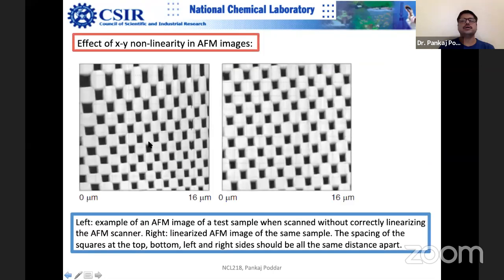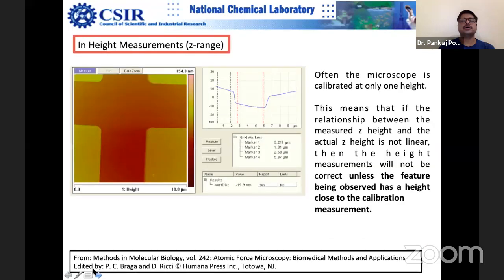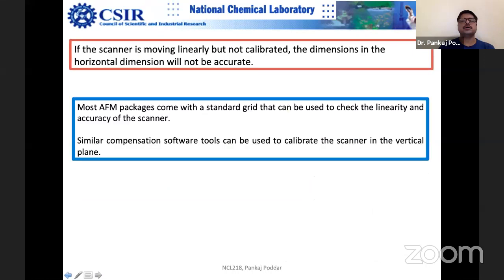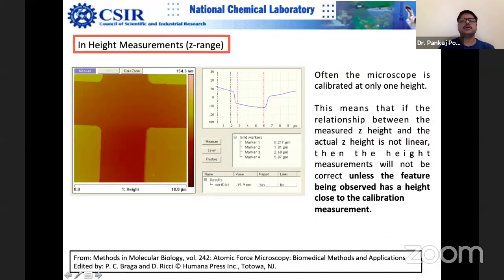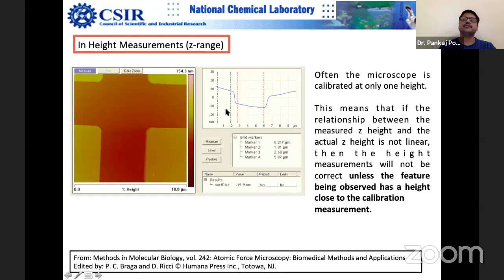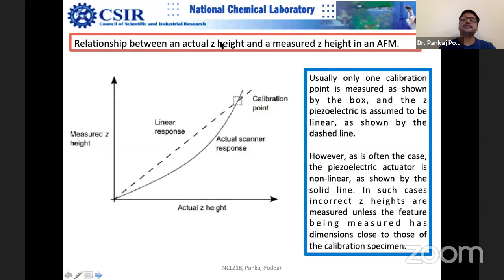There are software tools to fix the nonlinearity problem. You should be aware that you should not be publishing artifacts. In Z height measurements there can also be nonlinearity: ideally the response should be flat and linear, but it is not. The relationship between actual Z height and measured Z height deviates from linear. If you took a one-point calibration and drew a straight line, you are expecting a linear response, but the scanner actually moves nonlinearly. Scanners must be calibrated at multiple voltage points covering a broad range.